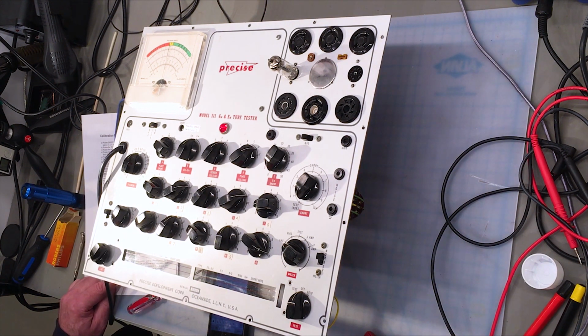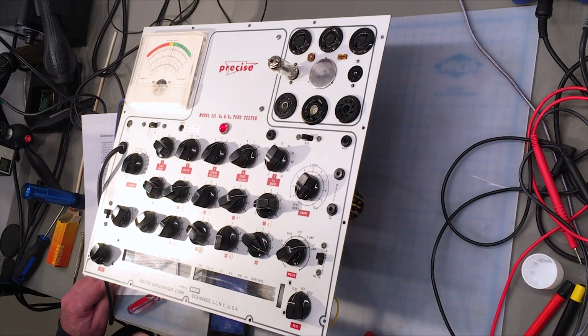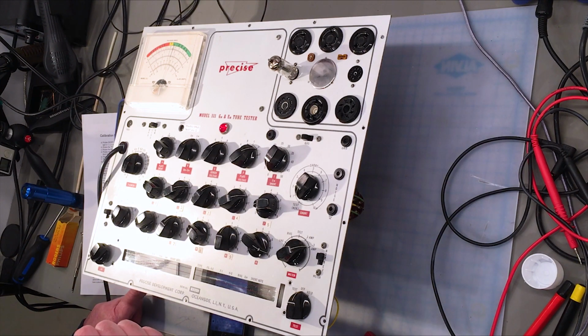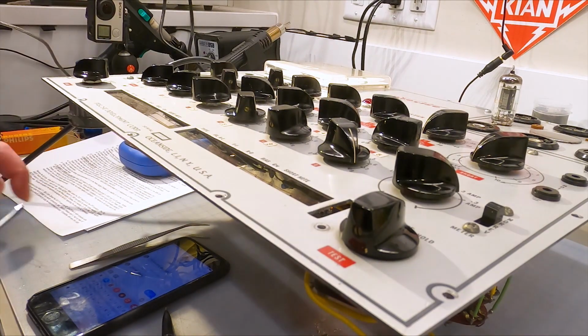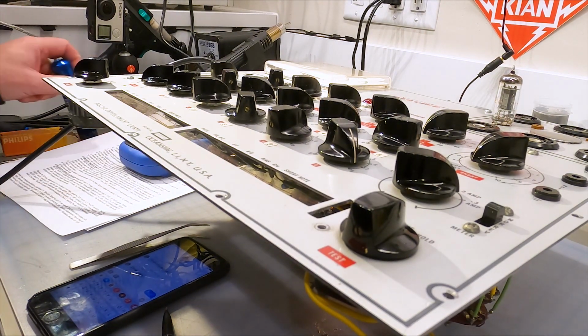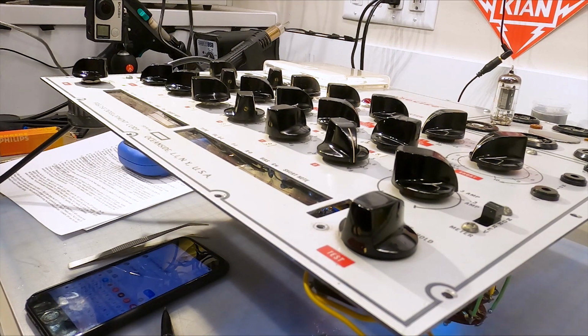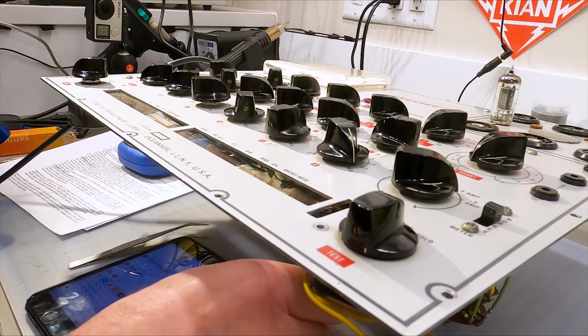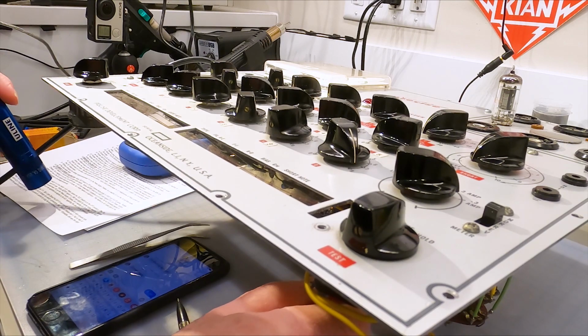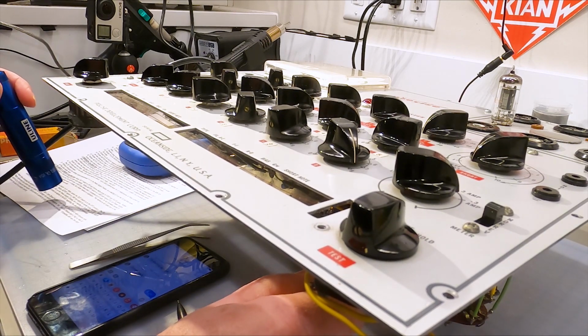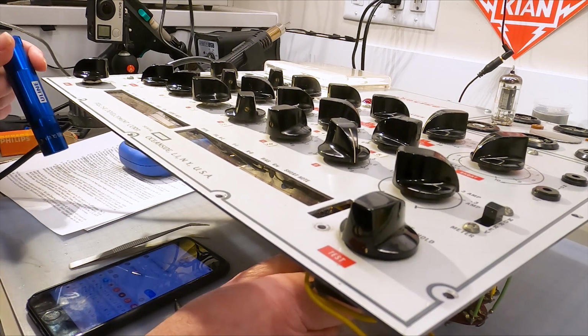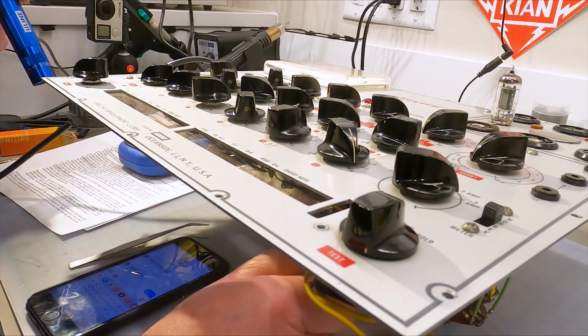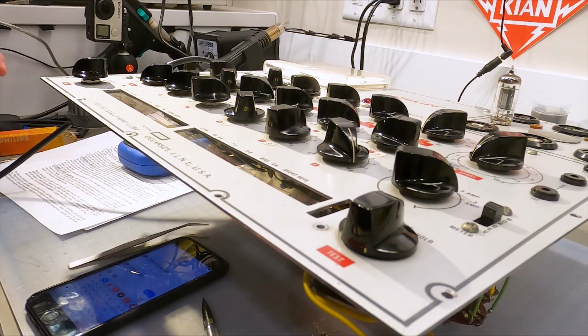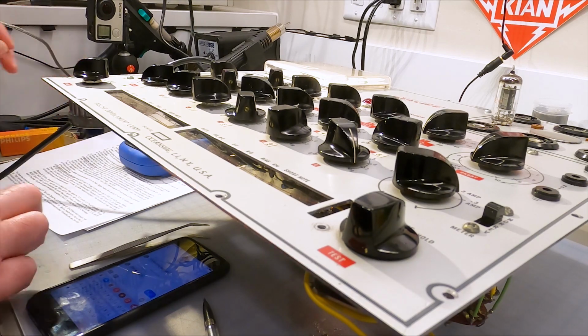Then we rotate the meter switch to 0.3 amps and adjust potentiometer P13 for a reading of 0.15 on the 0.3 amp scale. And so 0.15 would be center, and P13 is above P12 on the far right top of the power supply chassis board. And that's that adjusted. And we've now completed the calibration.